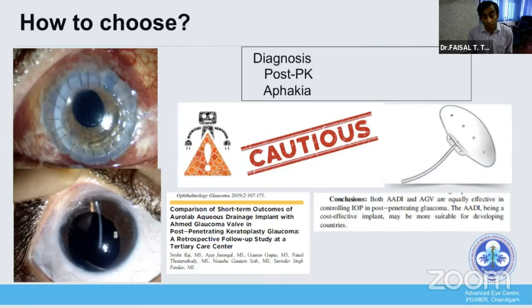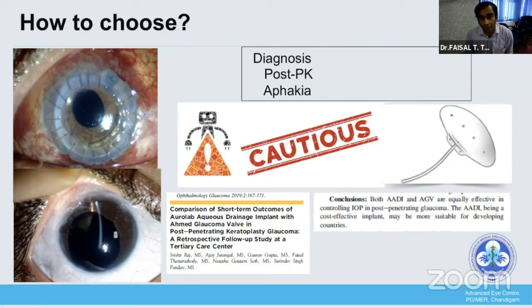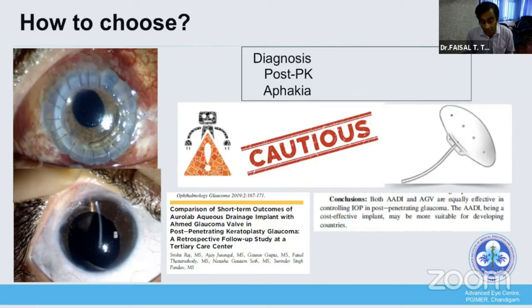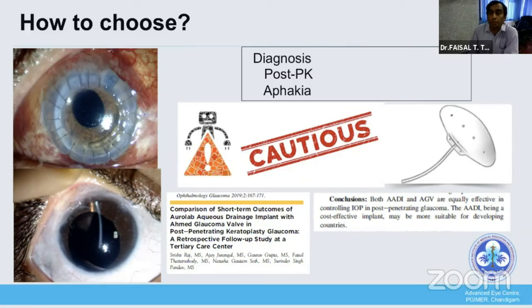Aphakic eyes are also high risk for hypotony and non-valve devices should be used very cautiously. In cases of post-penetrating keratoplasty (post-PK), if the eye is pseudophakic or phakic, one can consider a non-valve device. However, as most studies indicate, long-term hypotony can lead to graft failure, so non-valve devices must be used cautiously in this setting.